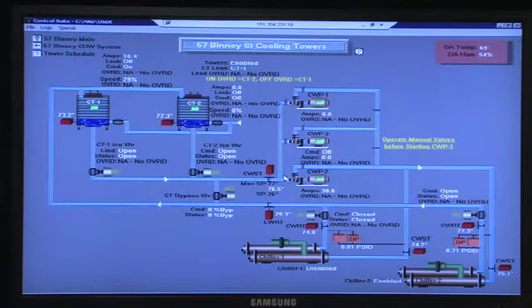There's no fan operation on cooling tower 2. It's just cascading down and just going through the fill, and that's it. That's why you're getting a higher basin temperature. There's no fan running on that one, it's just the water cascading down the tower. And as that condenser water gets above that max set point, right here, it'll stage this on. If it goes a couple degrees above that max set point, it's going to start to stage.